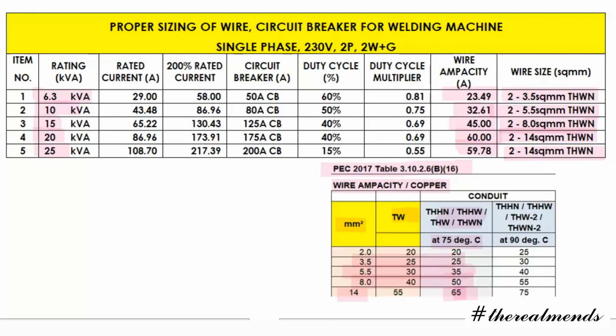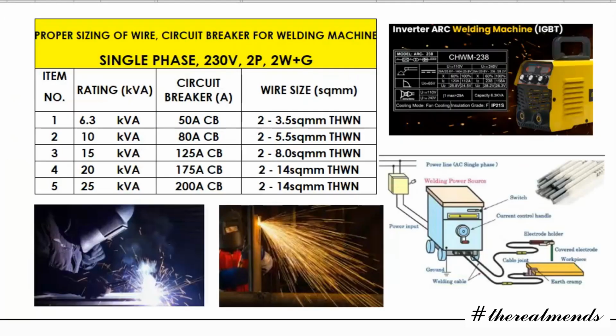Okay, to be clear, this is for the individual welding machines, okay? To sum up our discussion, again, we have this load schedule. If we have 6.3 KVA, we have a 50 ampere CB, with a wire size of 3.5. For 10 KVA, 80 amperes and then 5.5. For 15 KVA, 125 amperes and then 8.0. For 20 KVA, 175 amperes and then we have 14 square mm. For 25 KVA, 200 ampere CB and then 14 square mm THWN.